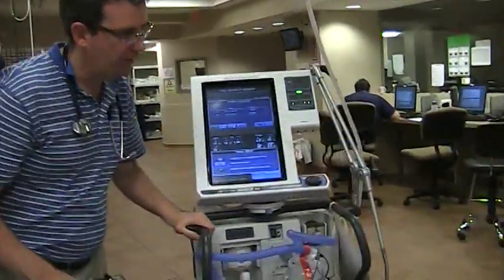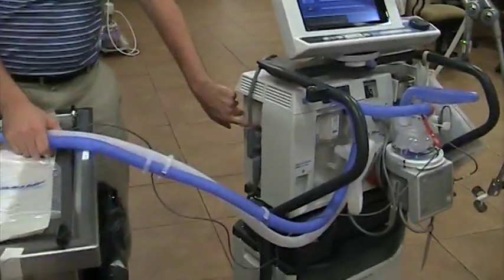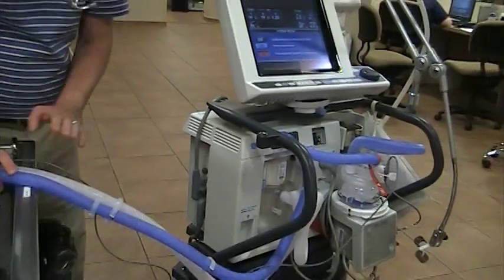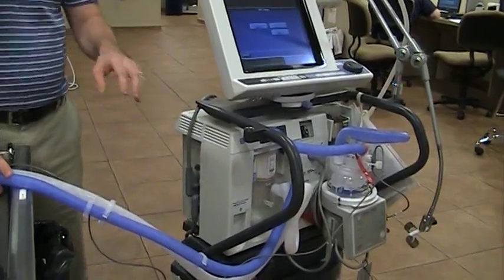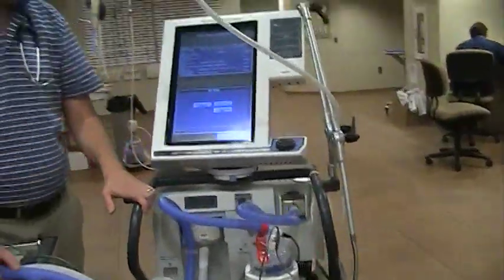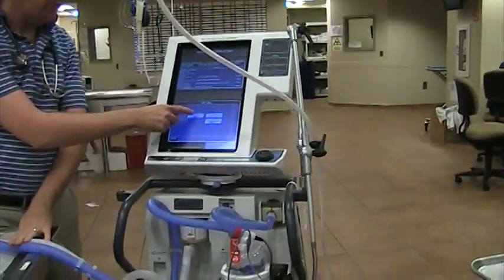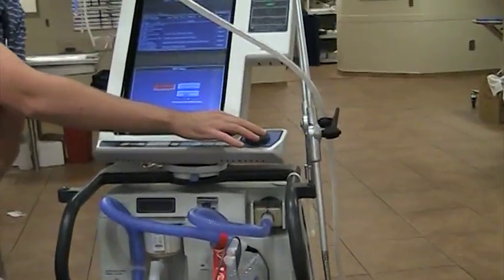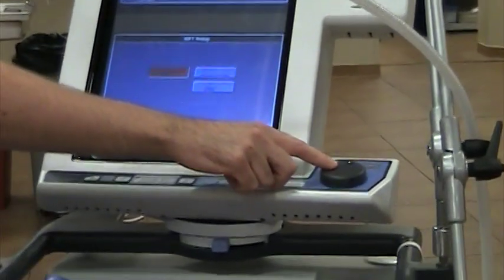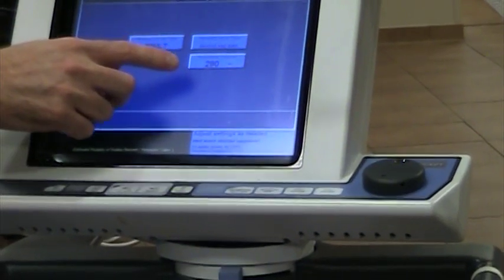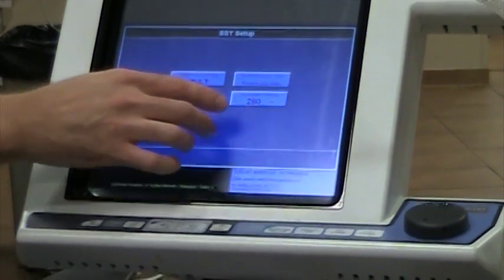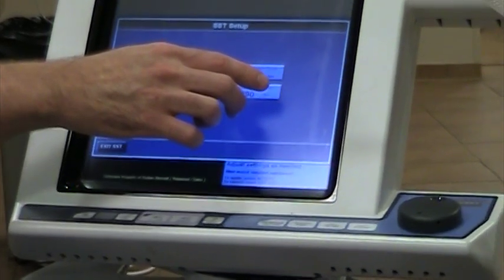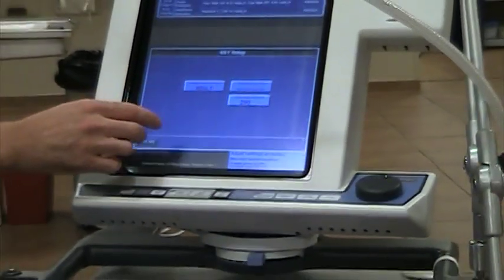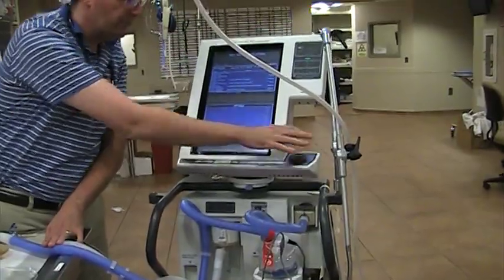So basically, the only other button that you're going to have to find is the test button, which is right here on the side. When you choose the short self-test, you just have to press this test button within 5 seconds, and then it'll get to this screen. You can press that button and then choose either neonatal or adult. We're going to choose adult. You don't have to worry about these right here. This is basically just saying that it's heated expiratory tubing, and that we have a humidifier which has a 290 mil volume. So now we're ready to go, so we press accept.